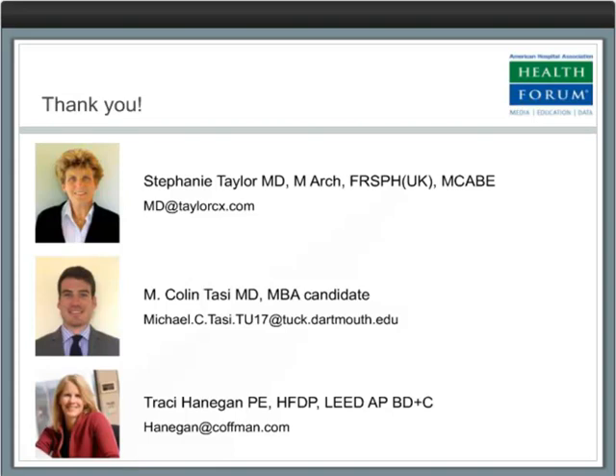Do we have more questions here? This is Tracy Hannigan. I see one that talks about addressing fuzzy ducted systems and says it seems like a serious infection control issue. I assume what's meant by fuzzy ducted systems are lined ducts, and yeah, that's a pretty bad issue. I'm looking at a facility right now with some lined ductwork, and that creates an environment where if it gets wet with liquid water, you could have mold growth. I've heard of people becoming sick from it, and that's the primary reason ASHRAE Standard 170 doesn't allow lined ductwork in healthcare facilities anymore.